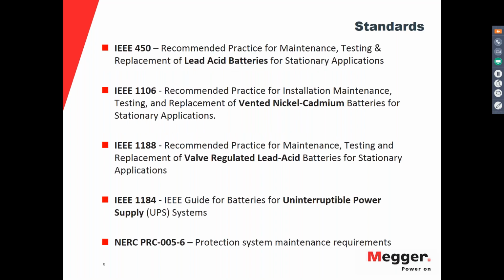In the world of batteries, we have a lot of standards. Each type of battery has its own standard, with recommended practices for maintenance and installation. That's what we can use for reference, and it's strongly recommended to follow those standards, because professionals have met and put together these documents to guarantee that you can do very good maintenance. Everything is well explained in the standard, and you have a lot of guidance there. Each battery has its own document.